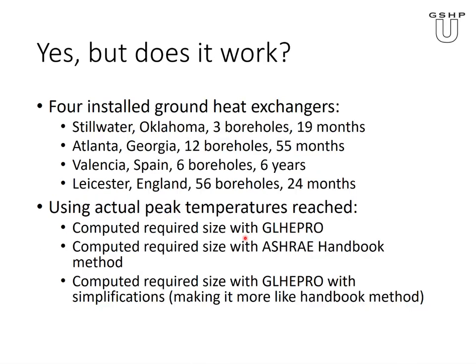A good question is, okay, yes, you have all this, but does it work? So we've done some validation. You may notice our example, like I showed you, was a 10-year example. We often size at 20 years, 25 years. There are no data sets that I'm aware of that extend to 20 years. There may be some other data sets now, but about 5 years ago or so, this was all that we could find. So we had run a system with 3 boreholes here for 19 months.